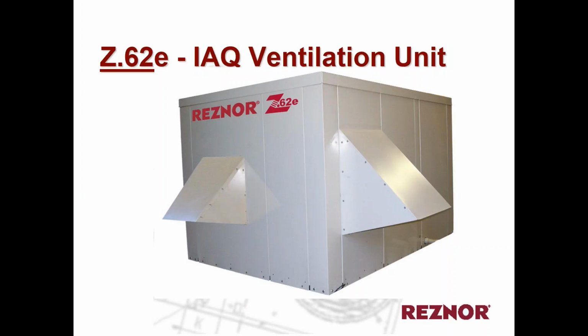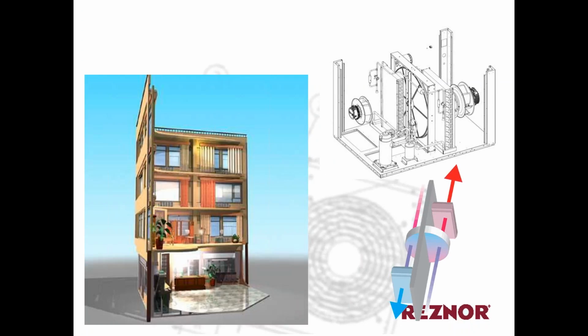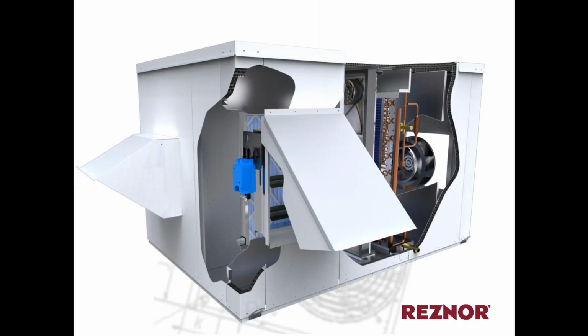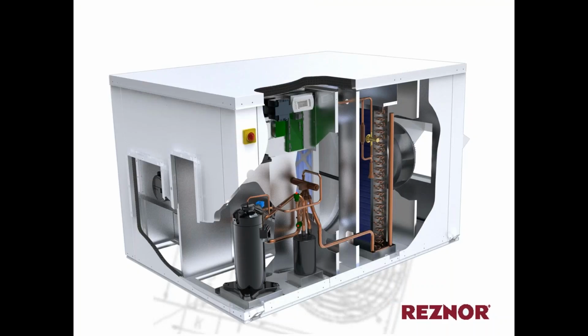And the last item I'd like to talk about today is our indoor air quality or ventilation unit, which is the Z62 unit. Essentially what this unit does, it allows us to provide ventilation air, particularly for VRF heating and cooling systems, by offering a heat pump with an energy recovery wheel wedged in between the heat pump coils. This unit pre-treats the air before it reaches the building. And this is a great product and was designed by Reznor to match VRF systems that are out there today that have become very popular, particularly commercially with heating and cooling. And this fulfills the ventilation requirements for those types of systems.